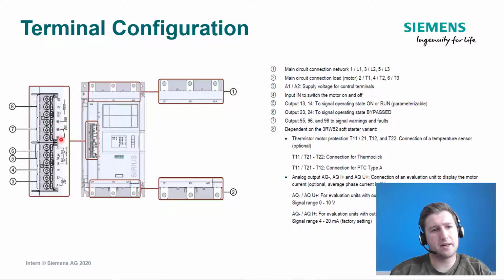This next configuration here is a normally open, normally closed changeover contact. This effectively signals whether the device is in fault or in warning. So if there's something awry with the soft starter, with this changeover contact, you can send a signal to an external signal to either a PLC or even an illuminated push button. It's just another way of signaling to an engineer that there's something incorrect going on with the device, or one of the parameters which you've assigned in the soft starter might have been breached.